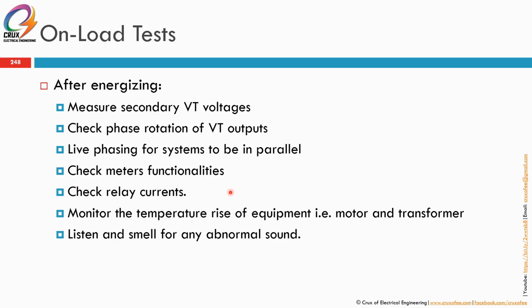So once you energize, you will do some measurement and checking of the equipment. For example, once you switch it on, measure the secondary VT voltage and check the phase rotation of the VT outputs. Okay, these are mainly for high voltage lah. For low voltage, you can check the phase rotation directly without any VT lah. So you must make sure that all are going in terms of clockwise lah, clockwise. And then live phasing for systems to be in parallel.